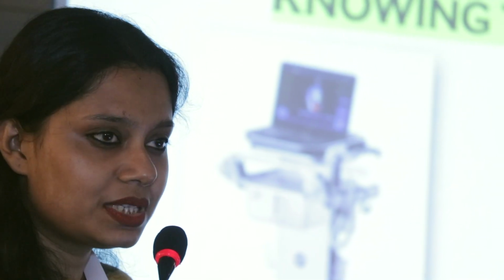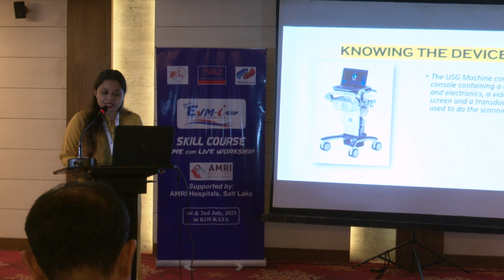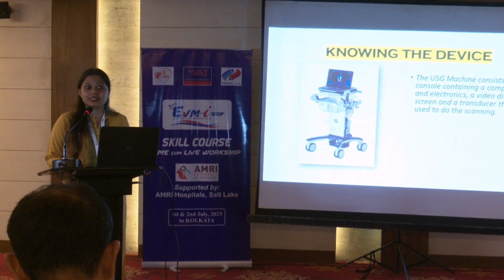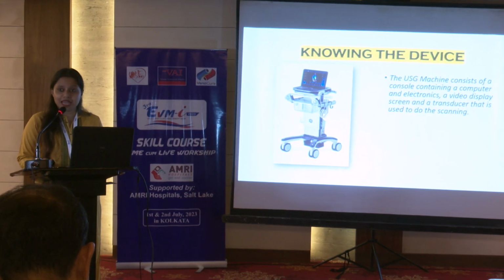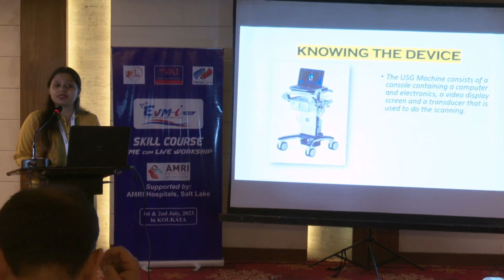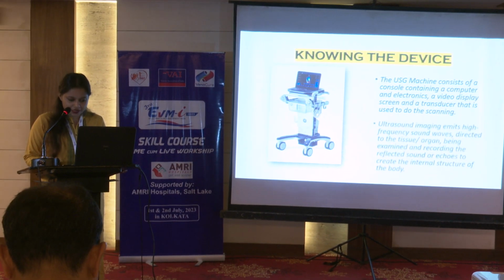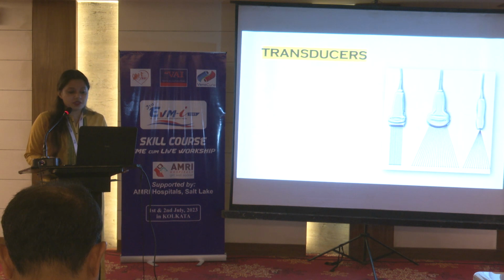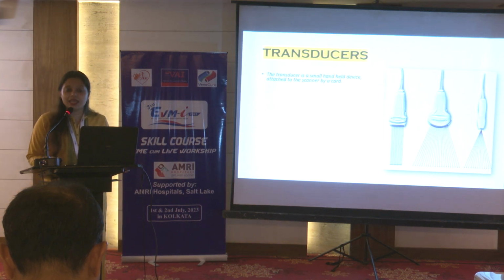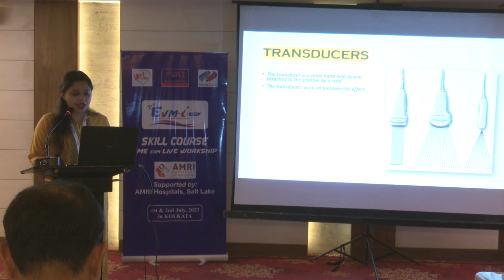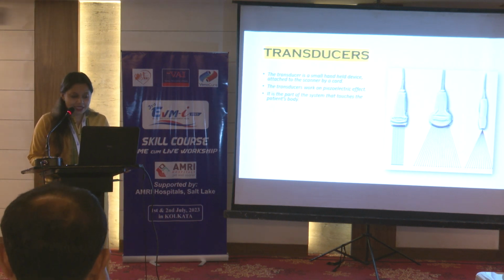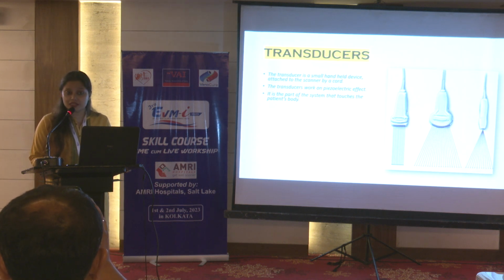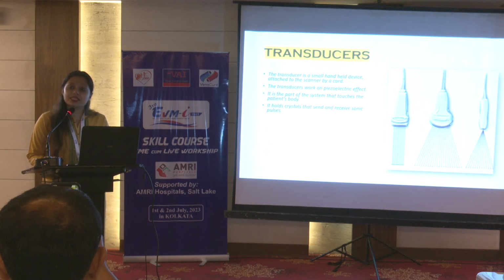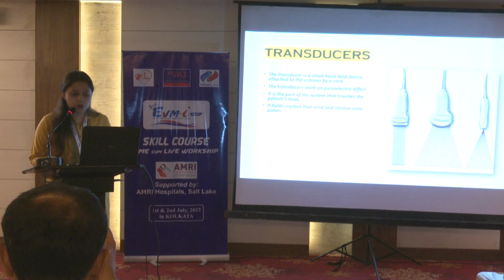An ultrasound is basically a device that has the electronics and computer consoles and a video display. It uses a transducer, the main instrument that sends sound waves down the body parts, in which the sound waves get reflected and we get the image of that particular part. Now the transducer. Transducers are handheld scanners that are attached to the ultrasound machine. It has the piezoelectric effect, and it is the main thing that touches the patient's body. It has crystals built into it that are used to receive and send the sound waves.